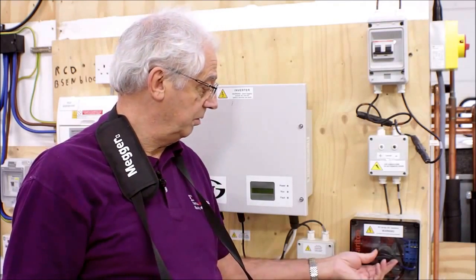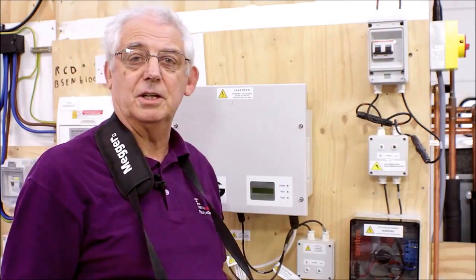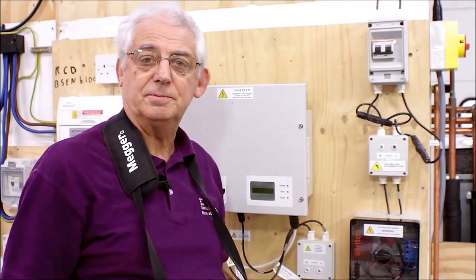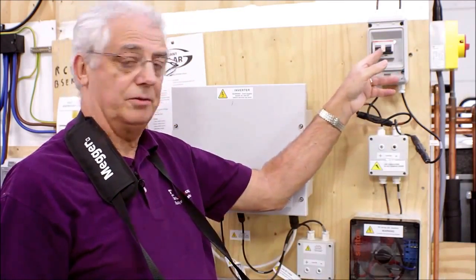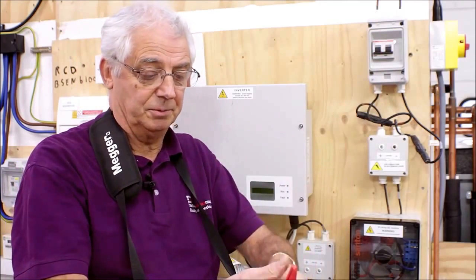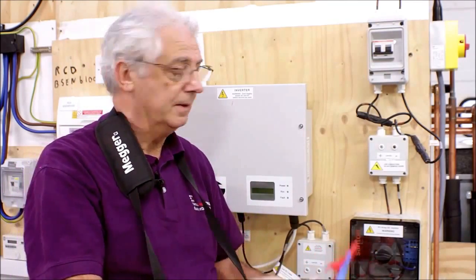And of course, if you're going back after a period of time to carry out a test, it's not particularly practical to get onto a roof and start trying to mess around disconnecting PV panels. So it's quite safe providing you follow the right procedures. What you would normally do is turn off the isolator and remove the cover and just use probes. But for us, we can do it by using this isolator here and these contacts. So the first thing I do is I turn off the isolator so the whole thing is completely dead.